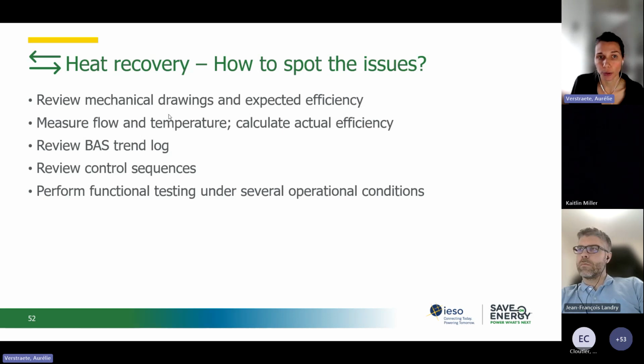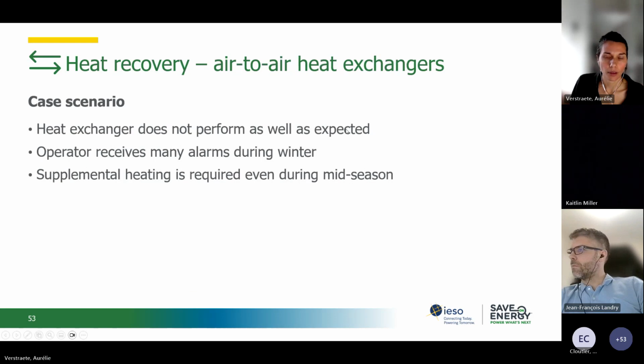You want to review mechanical drawings and expected efficiency. You want to measure flow and temperature and maybe calculate actual efficiency. Review BAS trend logs and review control sequences. And finally, perform functional testing under several operational conditions: summer, winter, maybe mid-season.